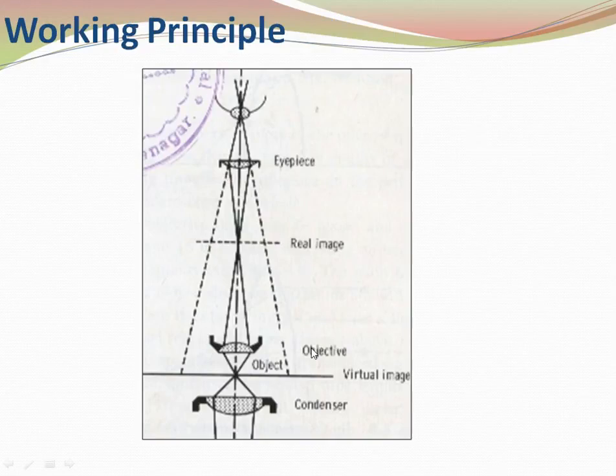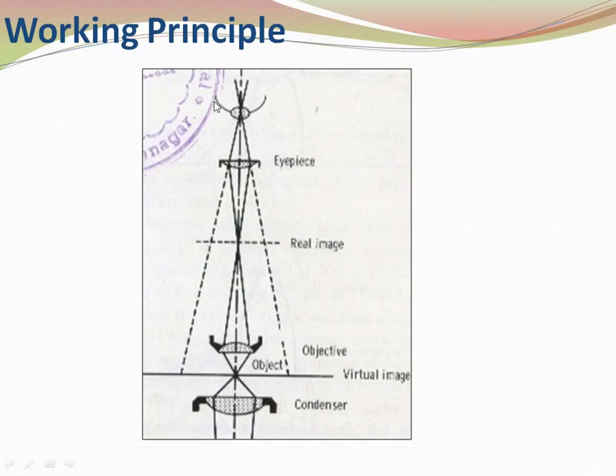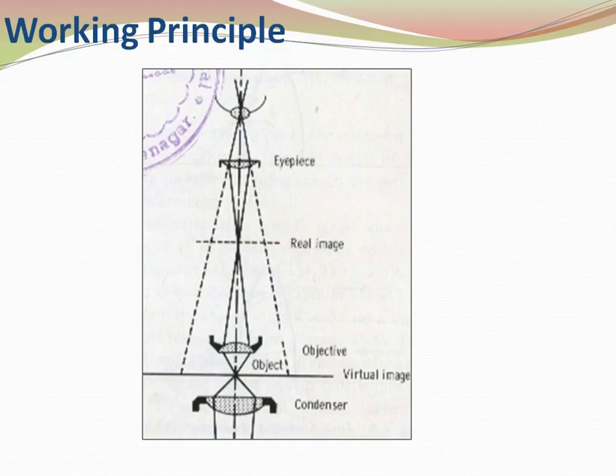Working principle of the microscope: there is a light source below, then a condenser, then the object or specimen on a glass slide, then the objective, and the eyepiece where we look. When light passes through the condenser, it focuses on the object. The condenser's function is to focus the light on the object. Light then passes from the object to the objective, which forms a real image between the eyepiece and the object. The eyepiece forms a virtual image.